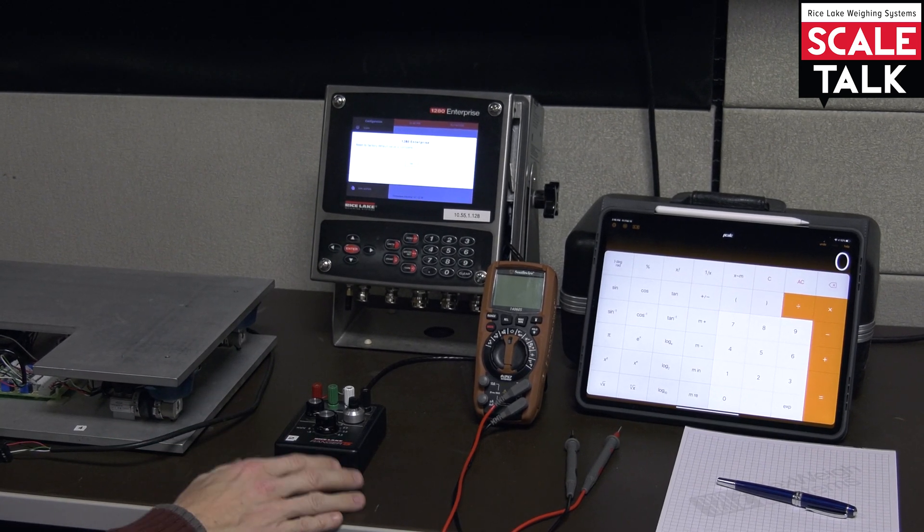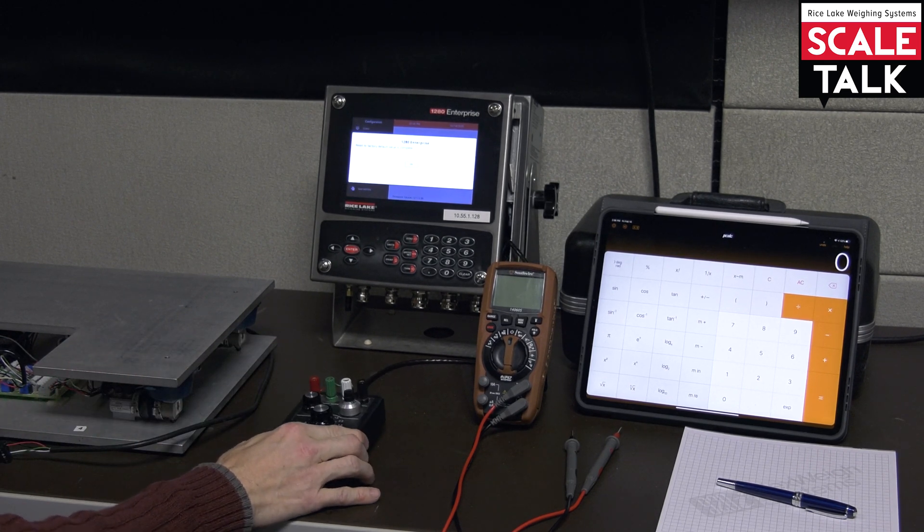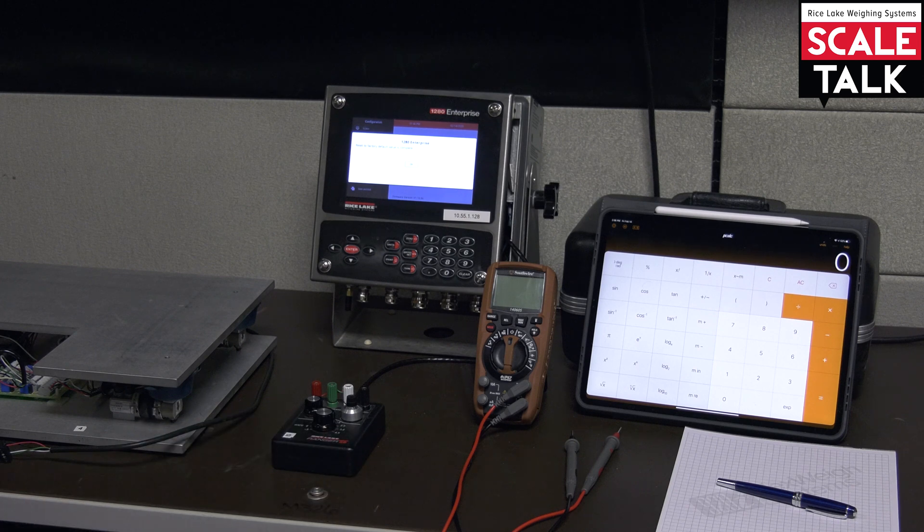So what we're going to show is how to try to calibrate our scale using just a simulator. Please understand that this is, of the four different methods of calibration that we've looked at, the least accurate and is not something meant to be used in a legal for trade application.